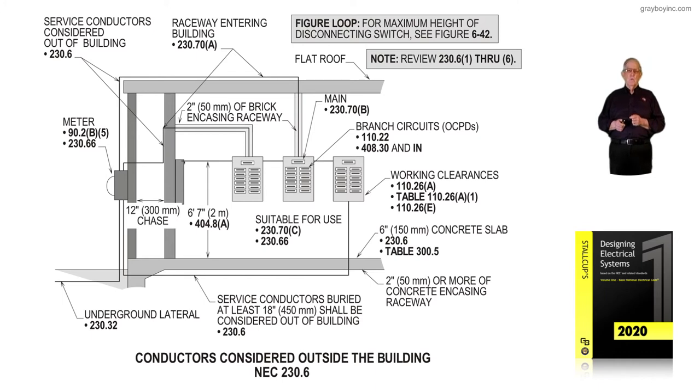Working clearances, as we've already been through, if you've been reviewing Chapter 5 and Table 110.26(A)(1), Section 110.26(A)(1), (2), and (3), along with the dedicated clearances 110.26(E) — we've already reviewed that information. Notice the concrete slab is 6 inches, and you're under that 6-inch slab, so you're considered outside the building until you emerge from the floor and the concrete slab to route to the service equipment. The authority having jurisdiction usually won't allow more than 6 feet 7 inches to the height of the main, as required in 404.8(A).